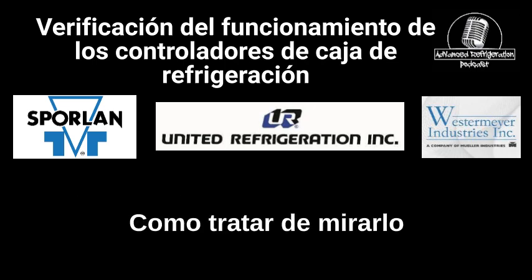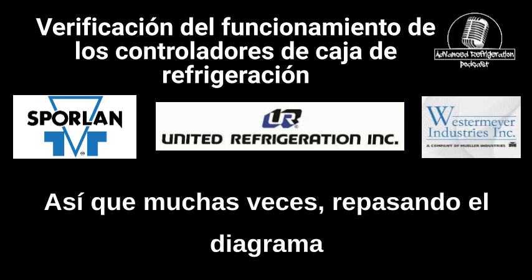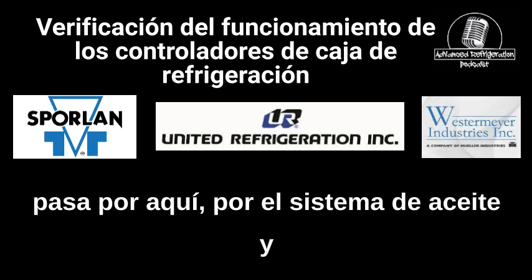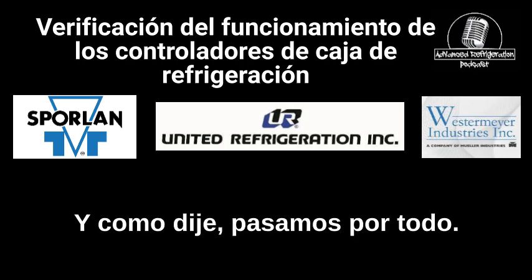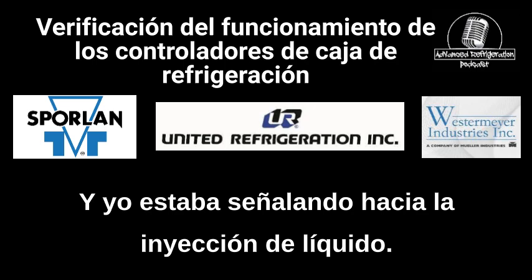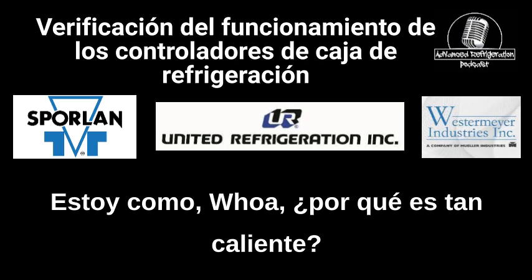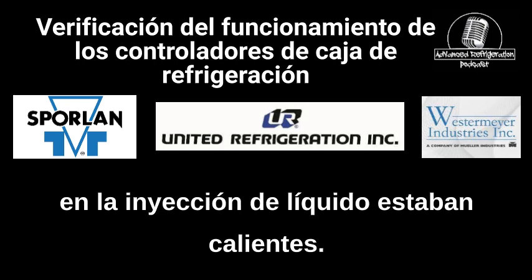Trying to look at it sometimes, you're like, I'm lost. So a lot of times going over the diagram on paper works: okay, the discharge line goes out, over through here, through the oil system, and then up to the gas cooler. Like I said, we went through everything and I was pointing over towards the liquid injection. I was like, yeah, this is feed. And I'm like, whoa, why is that so hot? I couldn't figure out why the valves on the liquid injection were hot.